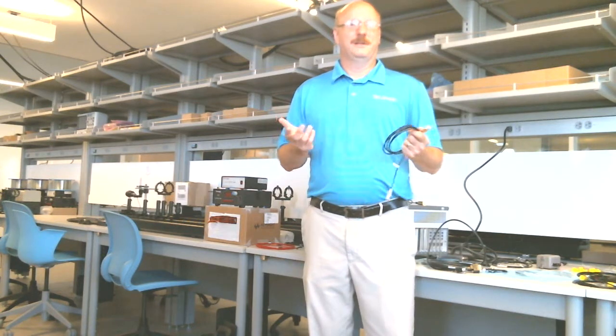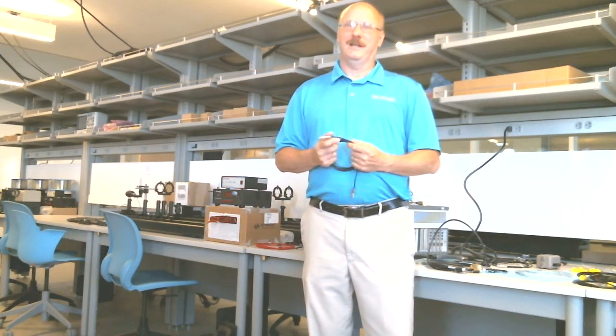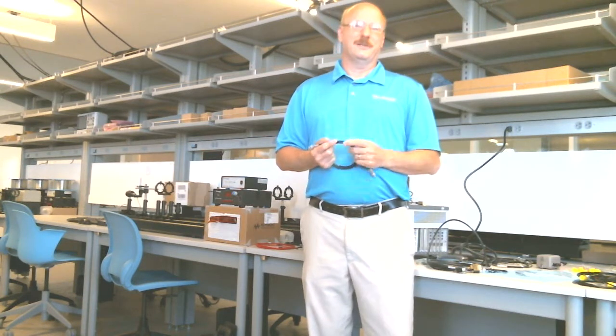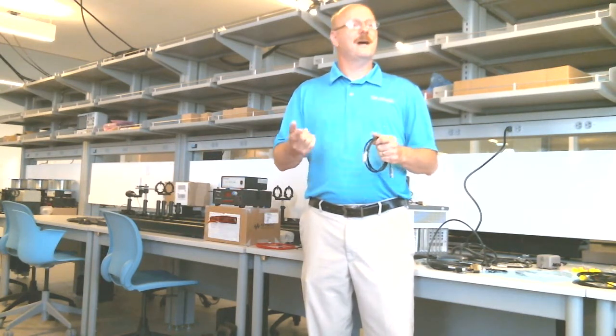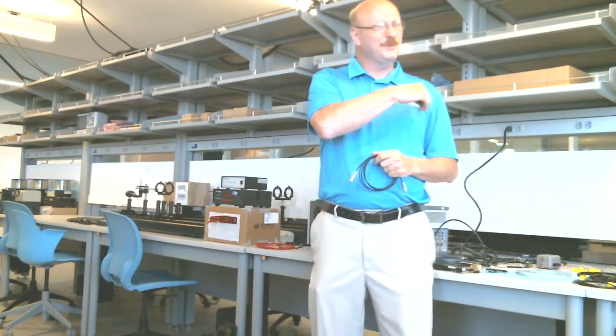So what does that do? It shorts out any capacitance and eliminates leakage. Because the leakage is still there, but it's sourced now by the buffer, not by the SMU, so it's not part of your measurement.